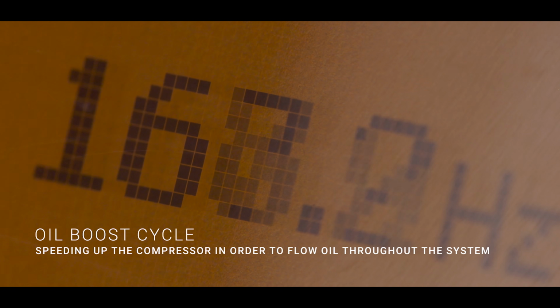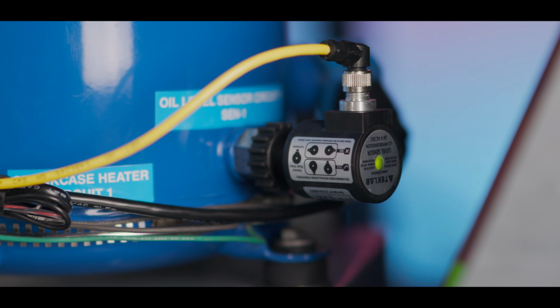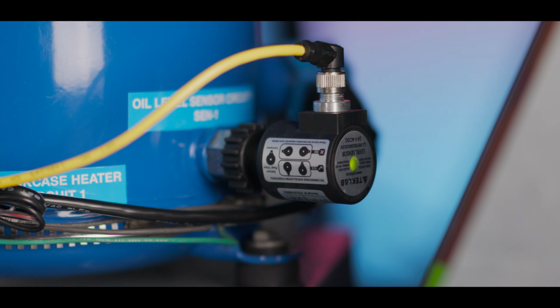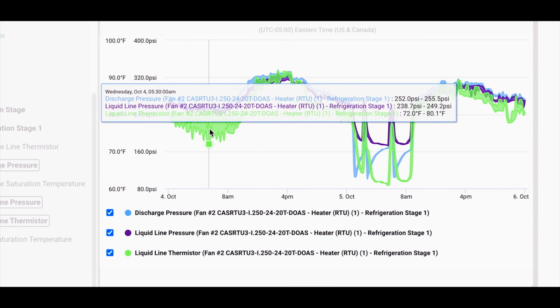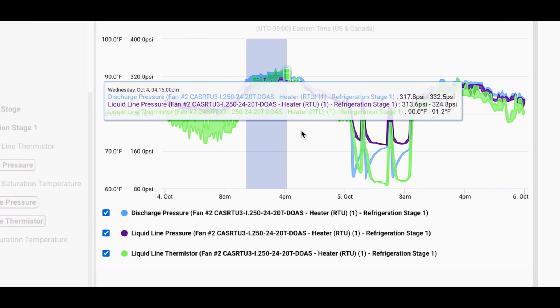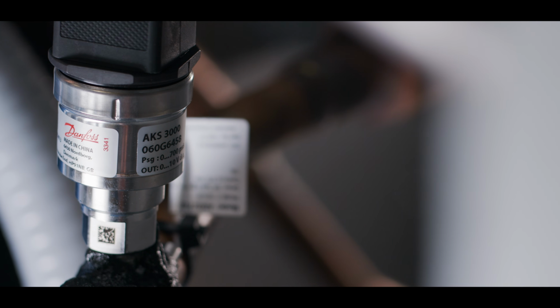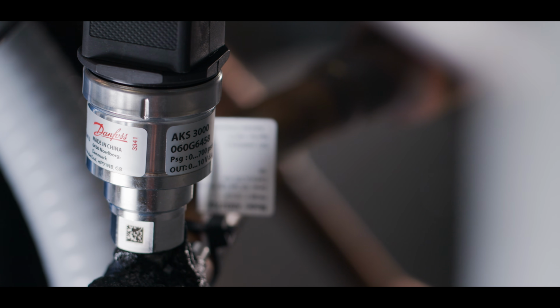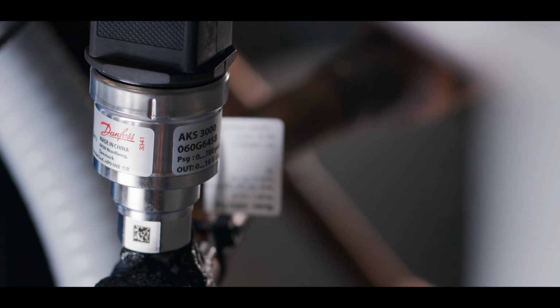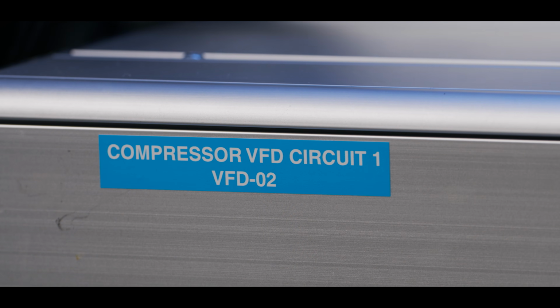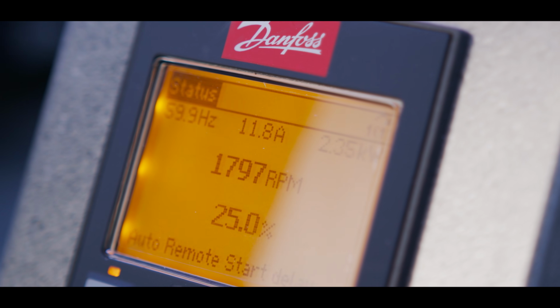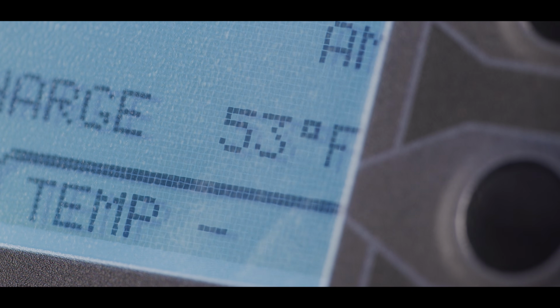We do that through oil boost cycles, and we monitor the presence of oil with an oil level sensor. We have an operating envelope where we look at different conditions of the way the compressor is operating, and we'll throttle that compressor to get into a safe range. So if pressures become too high or too low, we'll throttle the compressor to make sure we do everything possible to keep the unit heating and cooling when it's most needed.